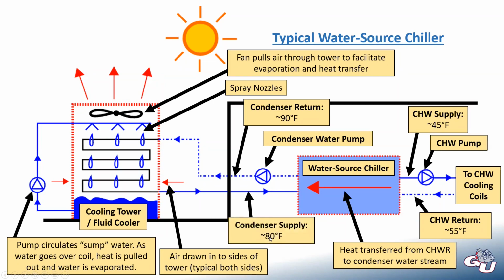And our water comes back cooler than what we sent it at. So if we were sending it in at 90 degrees, ran it through this cooling tower, it comes back colder, and then just starts over again. So this side of the system is constantly going between 45-degree water out and 55-degree water in, and this side 90-degree water out and 80-degree water in. Both sides have their own loop, but they are working together. We're just taking energy from the coils ultimately, moving that into the condenser water stream, and then ultimately rejecting that heat to the outside. So you can see there's a lot of stuff going on here, significantly more complicated than a basic air source chiller system.